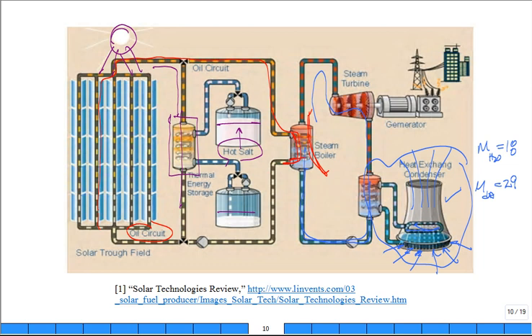As a design engineer, you size it and that to make it work for the over capacity of the thermal intensity in the hot part of the day with the sun's out. Then when the sun starts to wane, these valves change and you can then even not, you can shut off the flow of oil to the solar trough because maybe the sun is now set and the pump could run the oil backwards through the same heat exchanger.